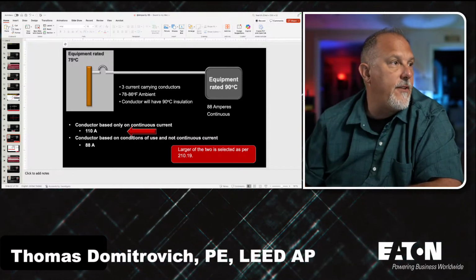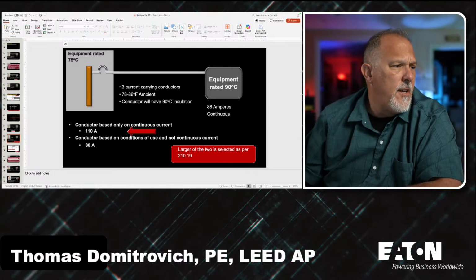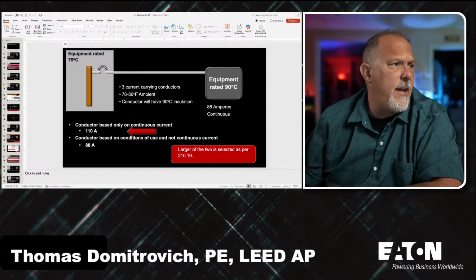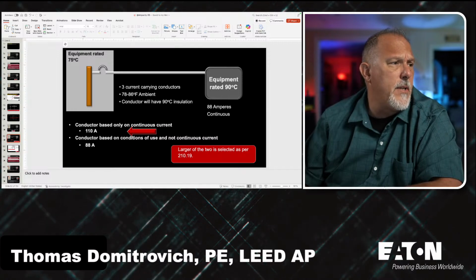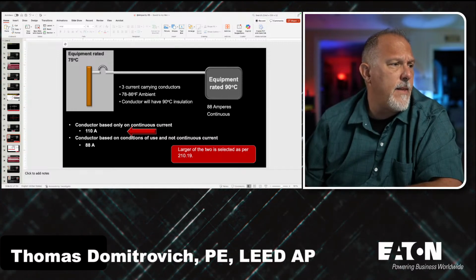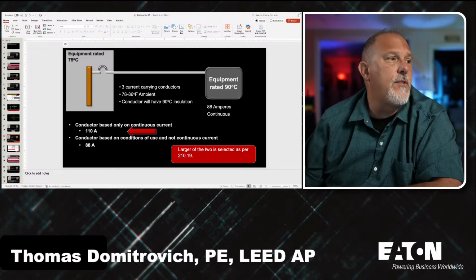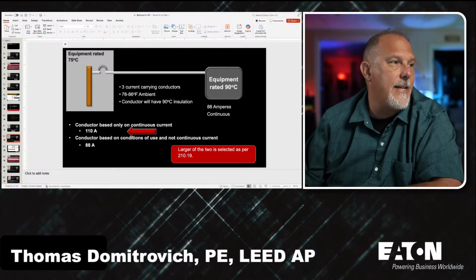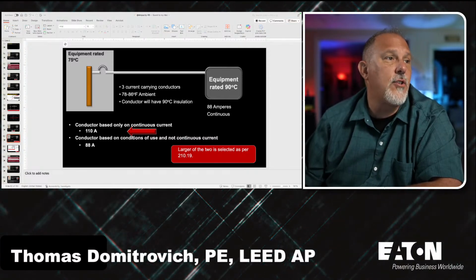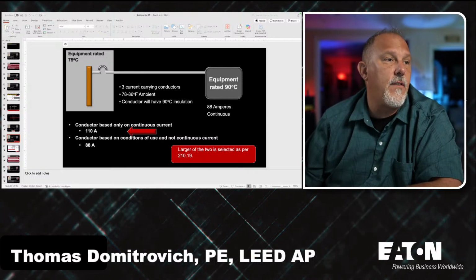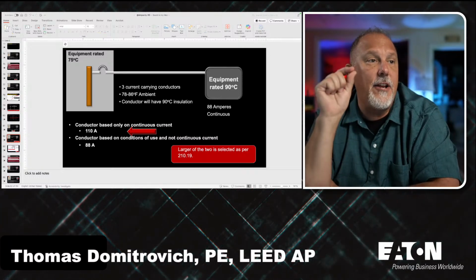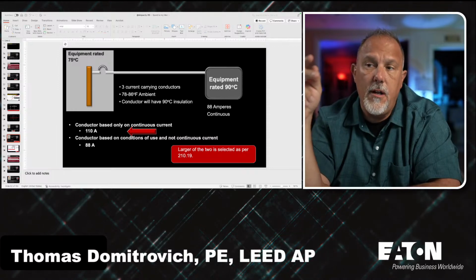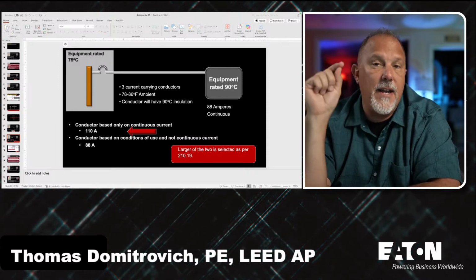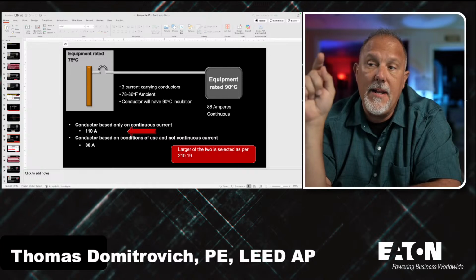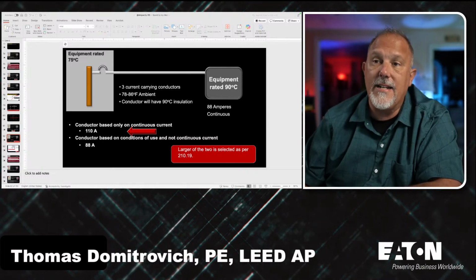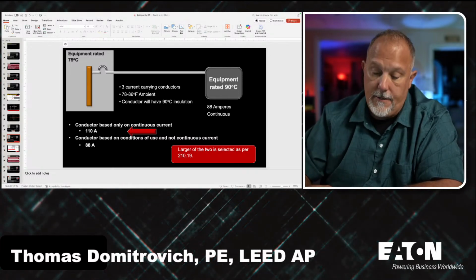What did the code say in 210? No, I'm in 240. 210.19, there it is. 210.19 tells us I have to have a conductor that has an ampacity not less than the larger of these two. In that case, my ampacity cannot be less than 110 amps. So that's the first gateway.